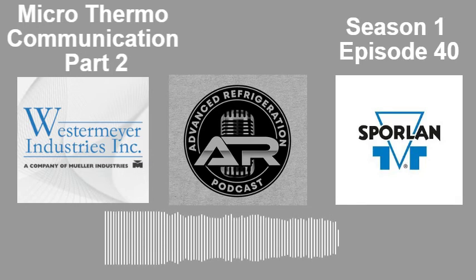That's pretty damn good. Let me blow this up. I wasn't expecting something as tight as that. The blue is the set point, and the green is the actual temperature. So you see this case controller is working tight. If somebody doesn't do their due diligence, this can be super spiky and all over the place.